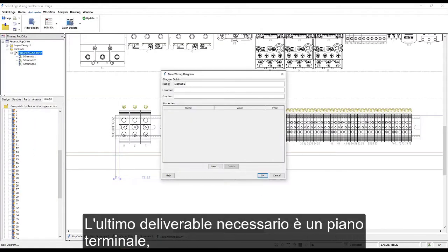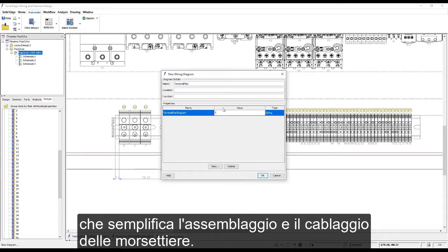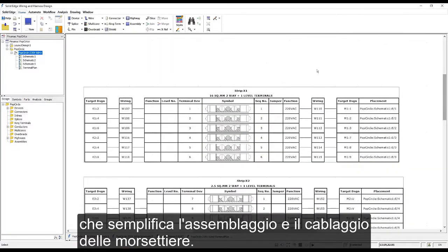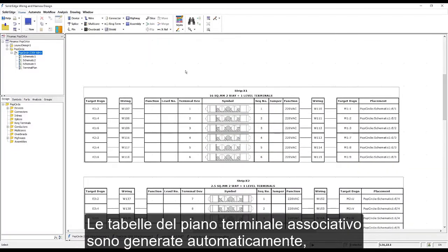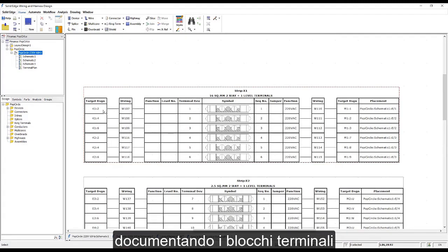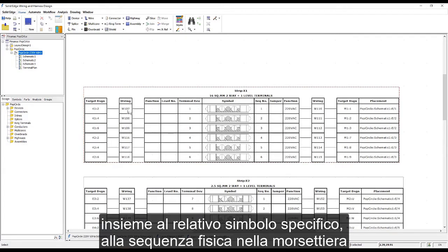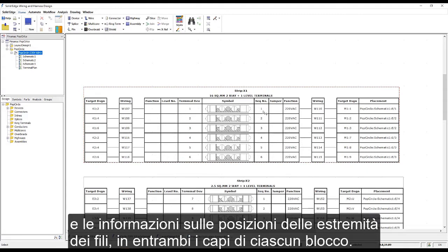The final required deliverable is a terminal plan which assists in the assembly and wiring of the terminal strips. The fully associative terminal plan tables are automatically generated, documenting the terminal blocks along with their specific symbol, physical sequence in the strip, and details of where the wires terminate at both ends of each block.